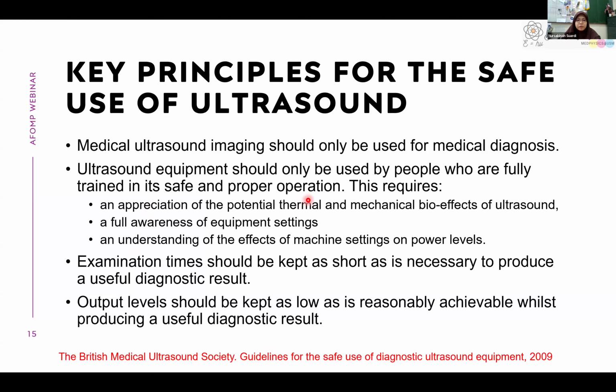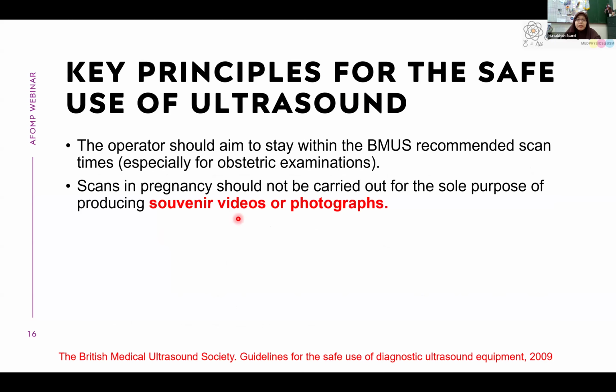You should also be fully aware of the equipment settings, because ultrasound is really operator dependent, and understand the effects of machine settings on the power levels. Examination time should be kept as short as is necessary to produce a useful diagnostic result. The output levels should also be kept as low as reasonably achievable while producing a useful diagnostic result. And the operator should aim to stay within the BMUS recommended scan times, especially for obstetric examinations.